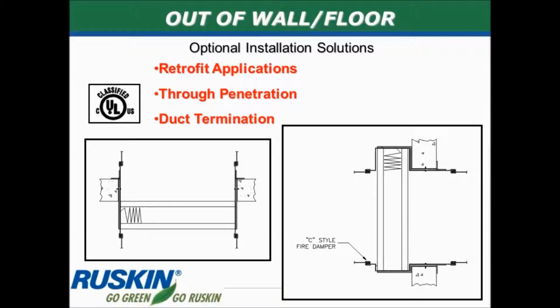Once in a while, the penetration of the ductwork through the floor or wall is simply not big enough to have a damper fit inside there. So what's used then is an out-of-wall damper. This is a special damper where the damper sleeve is coated with refractory fiber, and this maintains the integrity of the damper. As you can see in this illustration, on the left side, the damper is mounted in a floor, but the damper itself is actually below the floor. And on the right side, the damper is mounted in a wall, but the damper itself is not in the plane of the wall, it's on the left side of it. But that refractory fiber material maintains the integrity. When the damper blades close, it's secure enough so that the partition itself now has its rating, whether it's 2-hour fire rating or whatever. But a special out-of-wall damper can be used in these very tight situations.